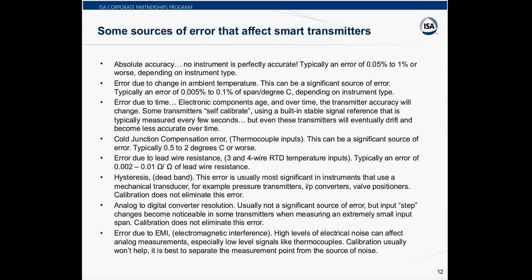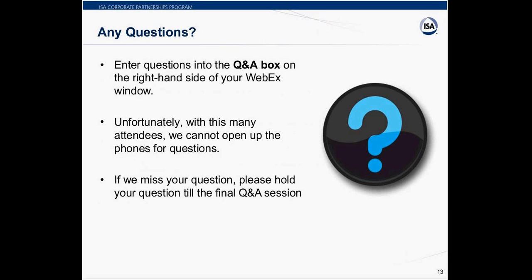Our first question comes from Andrew, who asked: will a HART communicator simulate the transmitter? The HART communicator is simply a communicator — it doesn't have the ability to simulate or to measure. So you'd have to use some other element to source the temperature, such as an RTD decade box or something that can source resistance, or even better, a calibrator.